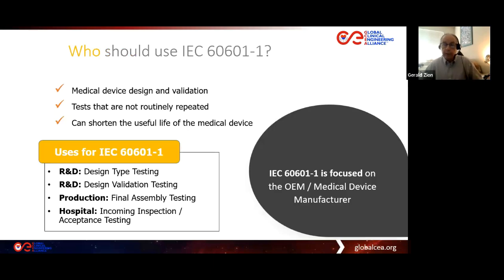All right, so who should use IEC 60601-1 electrical safety? This is focused primarily on the medical device manufacturer. It's their responsibility to verify that the device is safe and effective from an electrical safety point of view during device design and validation. The tests are not routinely repeated. By the way, they also need to be done in the factory at the end of the production line or in the production cell just before this medical device gets shipped to its end user location.